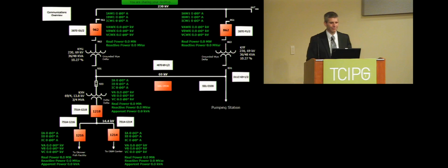So this is a quick example of a typical HMI you might see in a substation. It illustrates the point of this over-measurement. Up at the top is a 230 kV bus. There are 2 circuit breakers that bring the power down to transformers that step it down to 69 kV. And if we look at the top, we have currents being measured for both that are flowing through the circuit breaker. We're also over-measuring the voltages. So the voltages on the 230 kV bus are being measured by the relay on the left and the relay on the right. Similarly, we have the same thing down on the 69 kV.